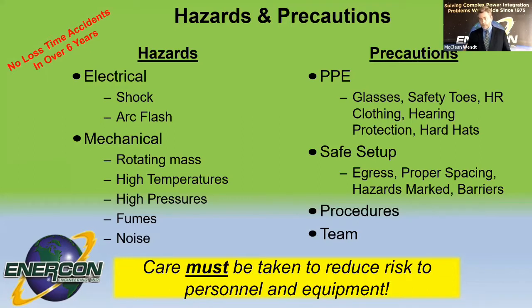So when we're setting up a test, we need to be mindful of all of these hazards, and we need to be mindful of egress and proper spacing, both for cooling and also to make sure that if a technician needs to get into a tight location, they're able to get out safely in case there's an incident. And then we also take care in marking all the hazards and setting up barriers to make sure that people don't accidentally or intentionally, for that matter, go into a danger zone.